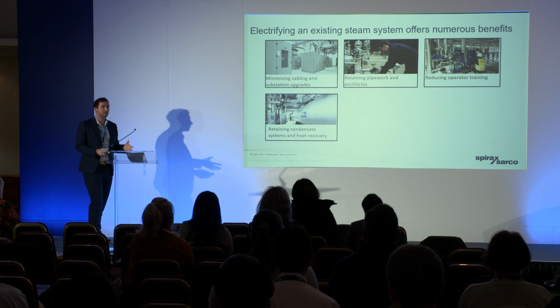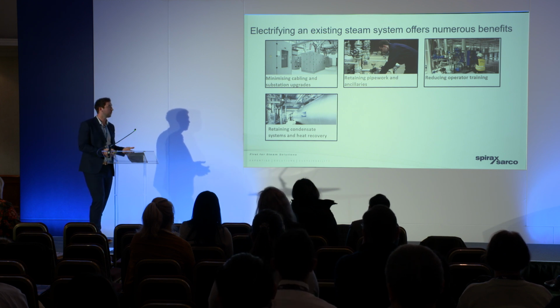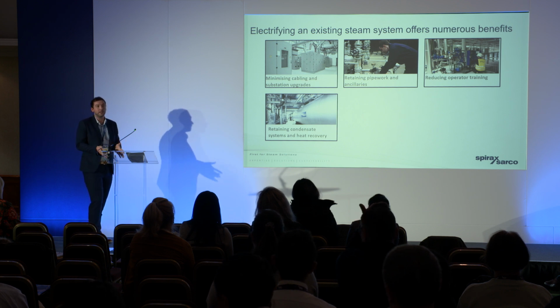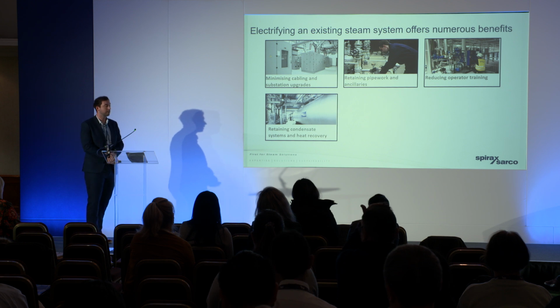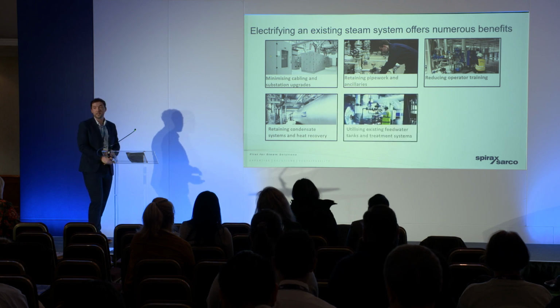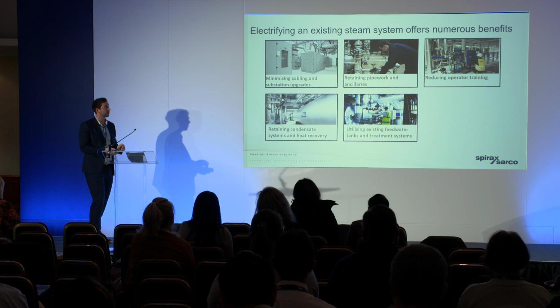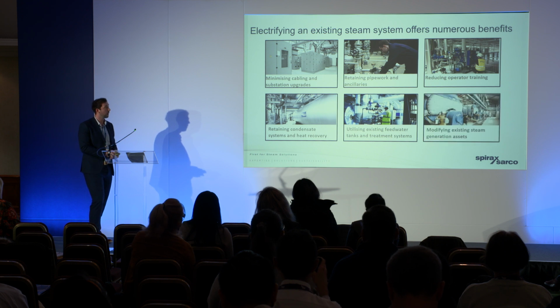At the end of the process, when the steam has been used and condensed, we've got the same condensate recovery systems, heat recovery, anything that's existing. The steam itself does not change, so we can utilize the existing system. And it's the same for the feed water. RO plants, softeners, they can all stay in situ because they're all fine to be used with the electrified boiler.